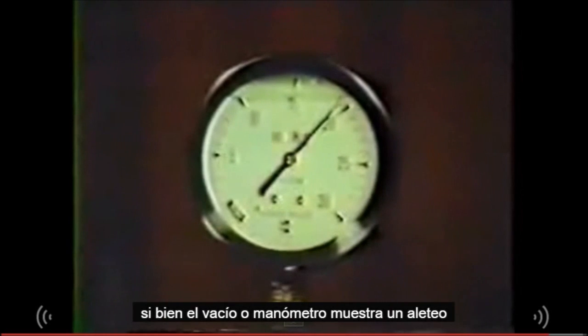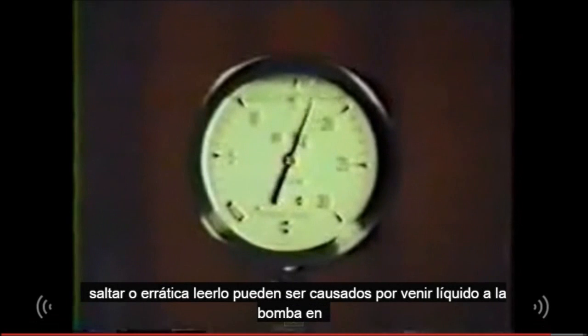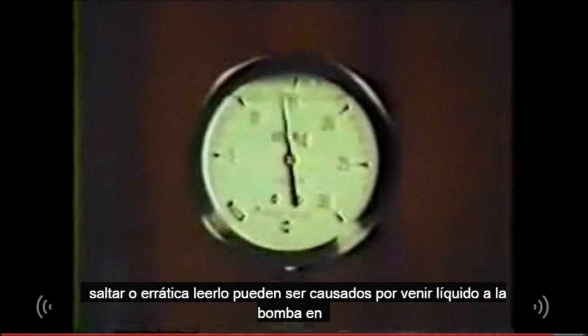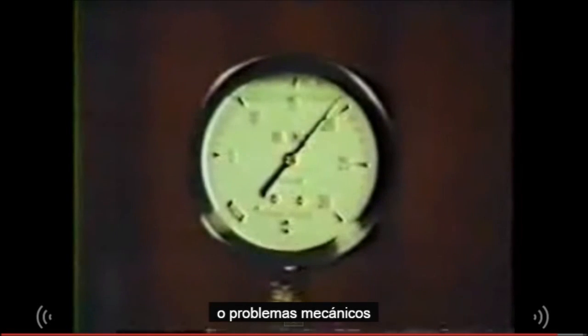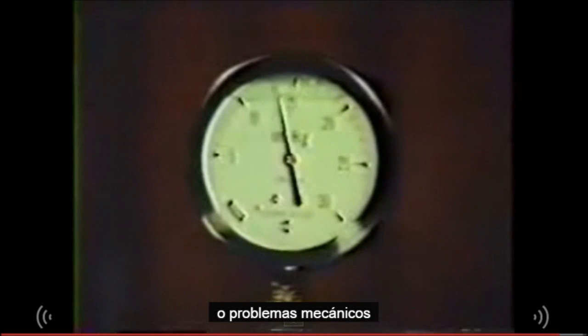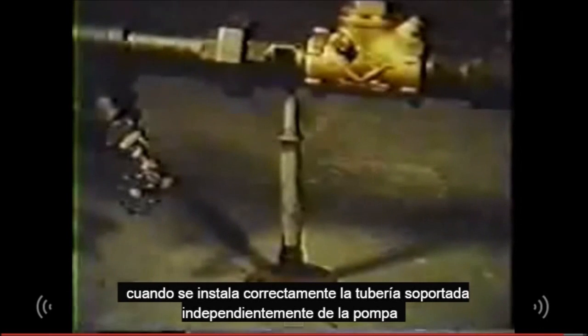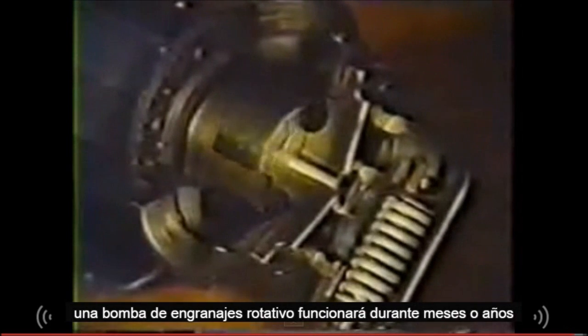If either the vacuum or pressure gauge shows a fluttering, jumping, or erratic reading, it may be caused by liquid coming to the pump in slugs, an air leak in the suction line, or vibration from misalignment or mechanical problems. When properly installed, with piping supported independently of the pump, all couplings aligned, safety relief valves set correctly, piping of the correct size, and good preventive maintenance, a rotary gear pump will operate for months or years before gradually losing its ability to deliver capacity or pressure.